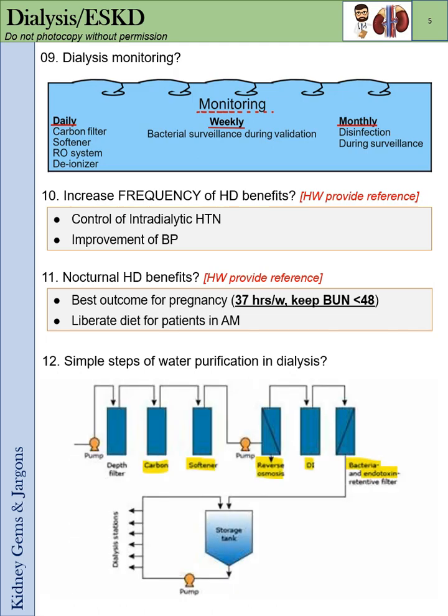Simple steps of water purification in dialysis: you start with a carbon filter, then the softener, then reverse osmosis, then the deionizer, and finally the bacteria and endotoxin retention filter.